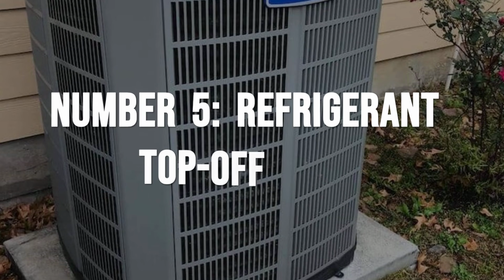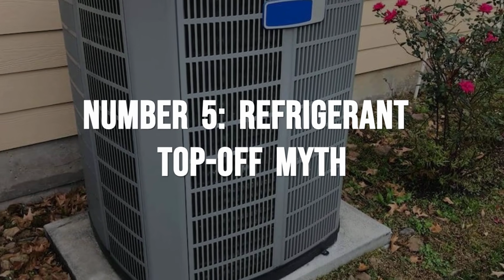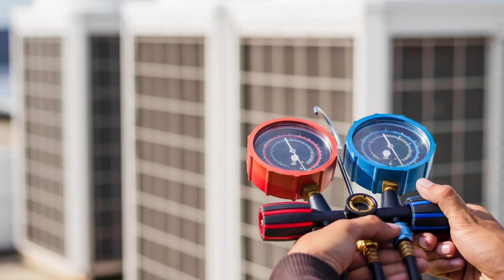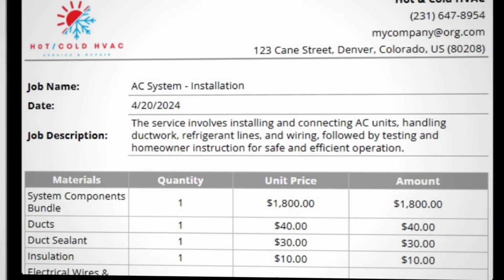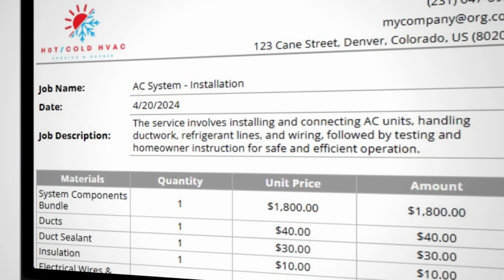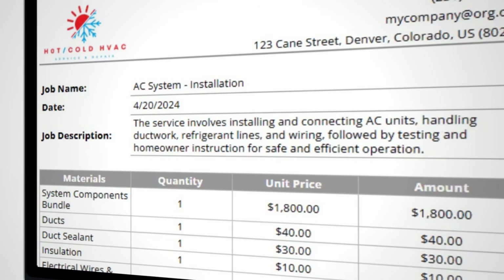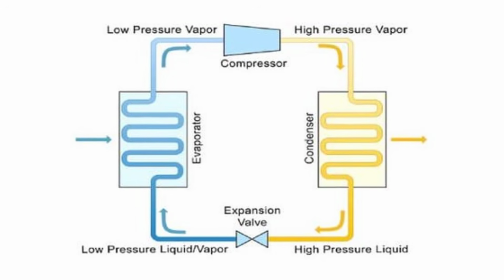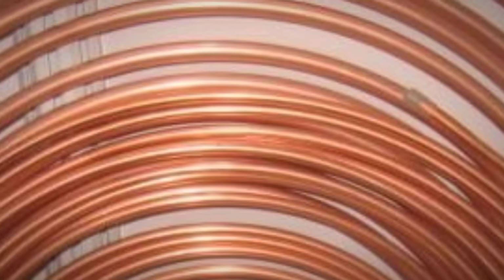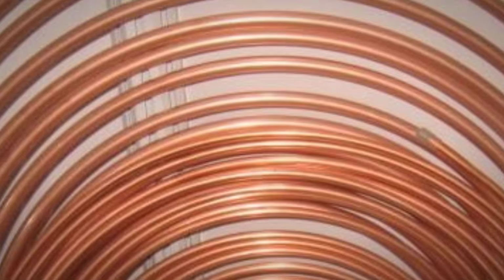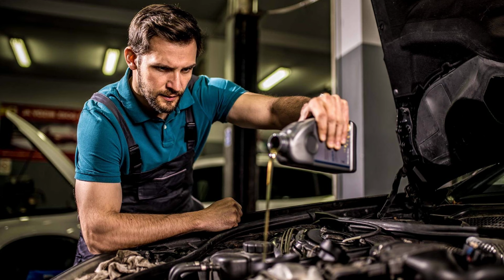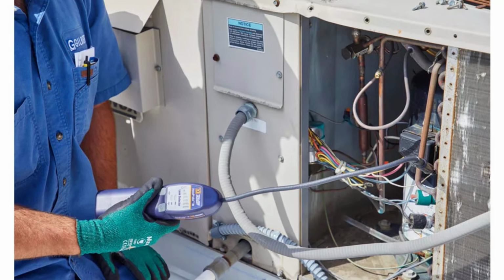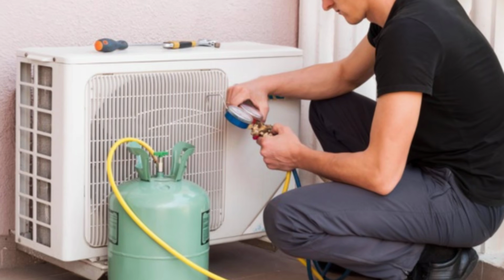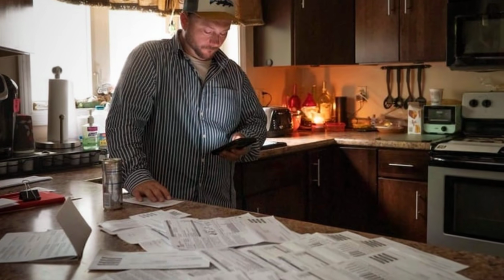Number 5. The refrigerant top-off myth. If a contractor tells you your system is a little low on refrigerant and charges you for a top-off, understand what he's really saying. A properly installed central air system is a sealed loop. Refrigerant doesn't evaporate. It doesn't burn off. It doesn't need topping up like engine oil. If the charge is low, there is a leak. Adding more refrigerant without finding that leak is a temporary patch. You'll be low again next summer, and he'll charge you again.